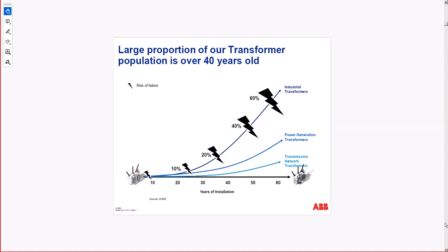service. You can see that industrial transformers have a high risk of failure once you get to 60 years in service, 40 years in service. The years in service are on the horizontal axis at the bottom, and then the risk increases up to 60%. So it's kind of going hand in hand: as the transformer ages, the chance of failure is higher. And you see these three curves. One is for industrial, the other is for power generation transformers, and the lowest curve is for transmission, for Hydro One. Industrial are the most exposed because they have a lot of switching and so on. Generation is second, and the network is third.